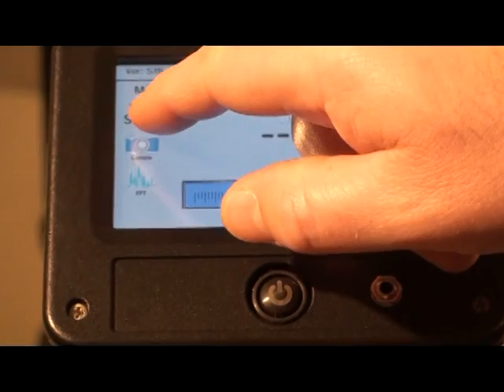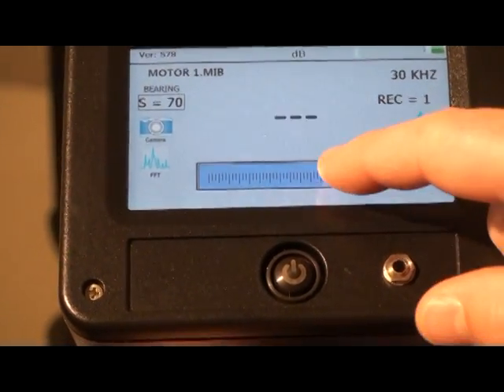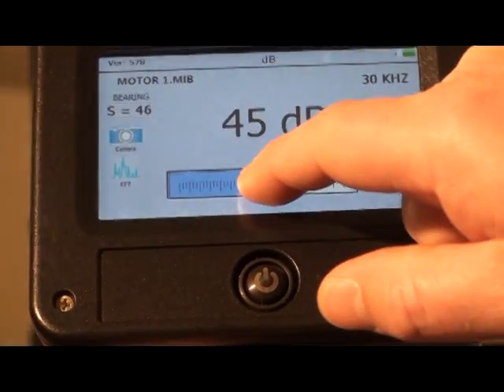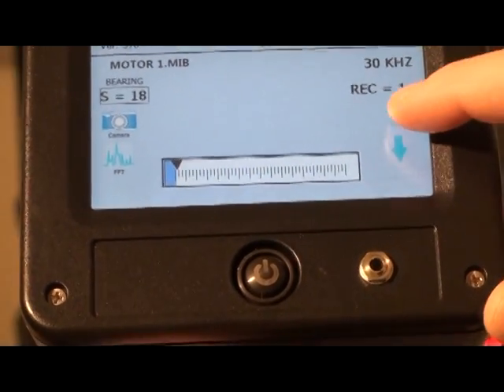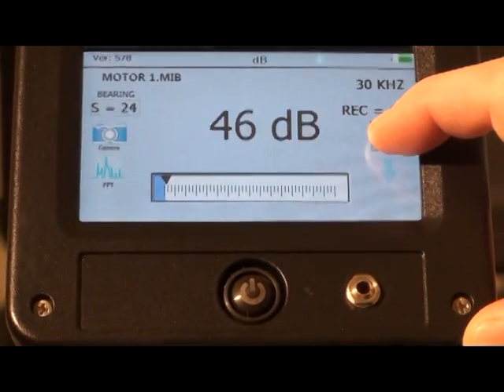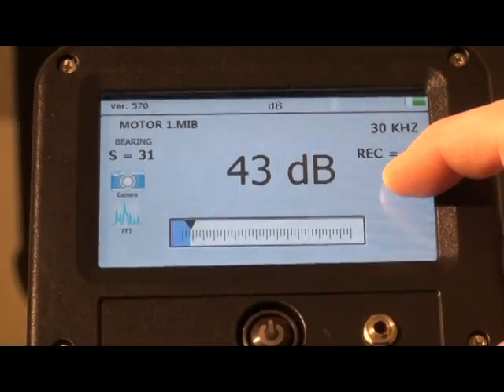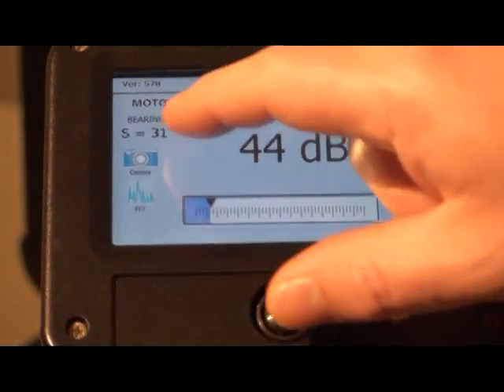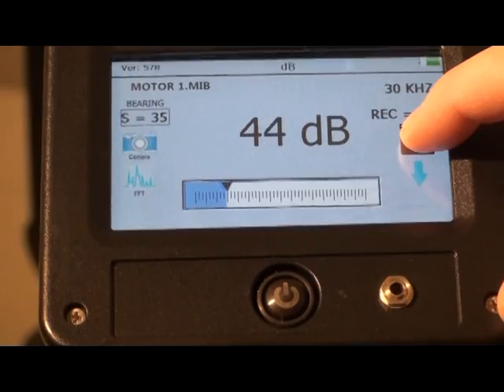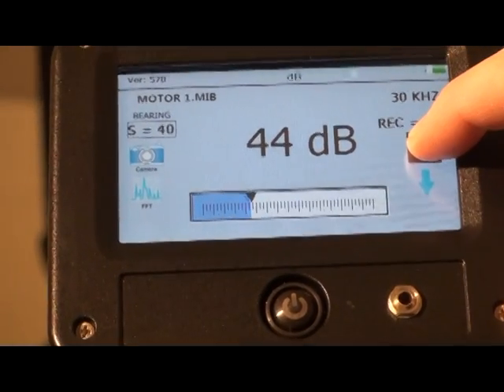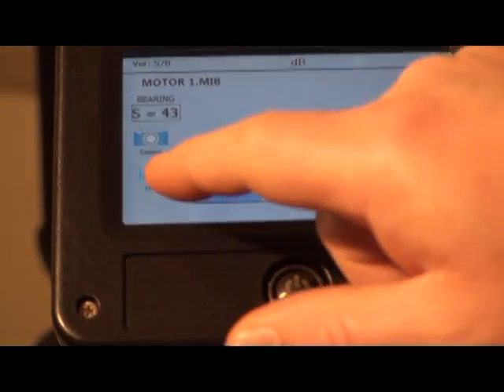To change the sensitivity, touch the S equals box. You can adjust the sensitivity with the up-down arrows or by touching and sliding the intensity bar graph. For optimum recording, adjust the intensity until the bar graph is at or about 30% of scale.